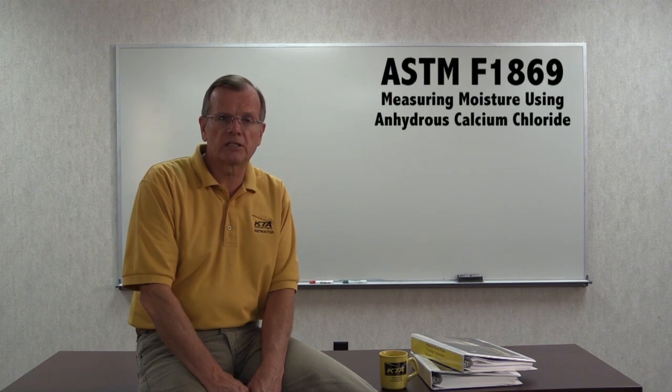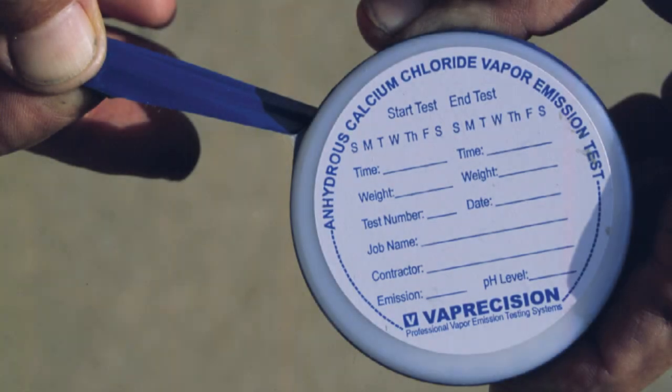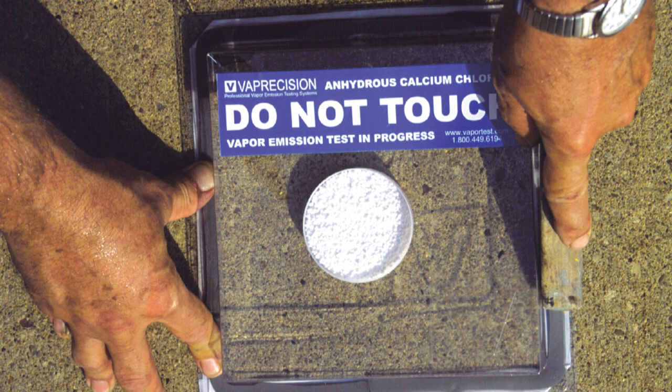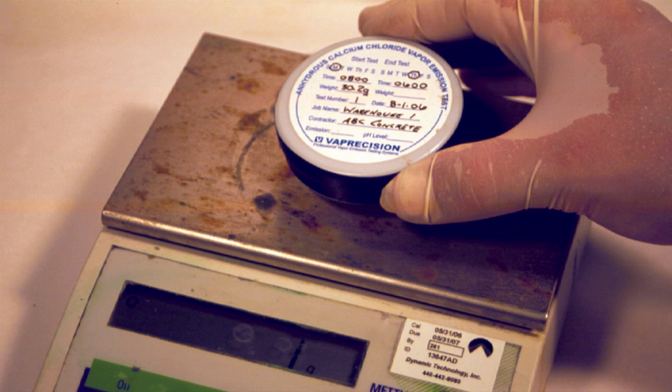The first, anhydrous calcium chloride, this method is addressed in ASTM F-1869. This is a non-destructive test that requires exposing the concrete slab to anhydrous calcium chloride for a given length of time. The anhydrous calcium chloride is stored in a plastic container and is weighed to the nearest tenth of a gram before you expose it to the surface environment, and again after exposure, to determine the increase in weight.